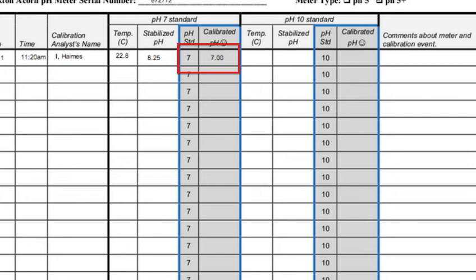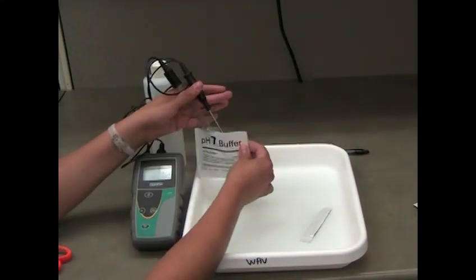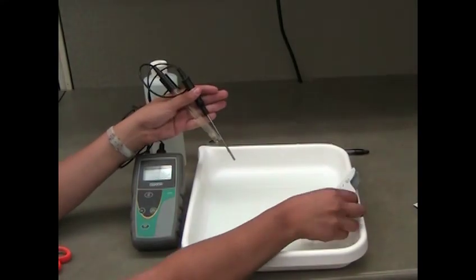If the value differs by more than 0.2, recalibrate the meter, and record the new calibration result on a different line of the datasheet. Repeat this process for the pH 10 buffer solution.